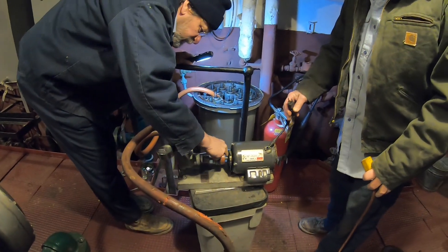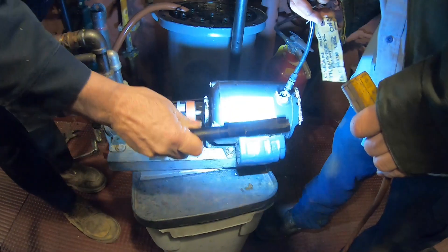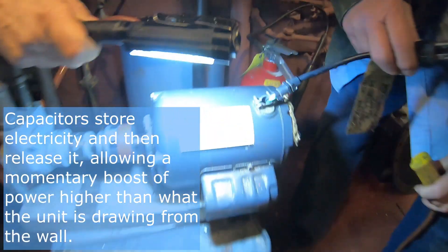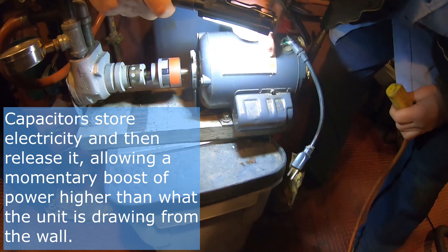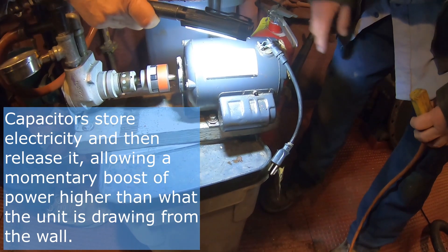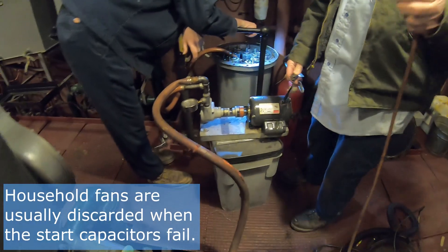But it's pumping. Why is it kicking out and off is what I don't understand — it's a pretty heavy load. What's it need for starting amps? More than we have? Horsepower amps — what's it say right there? Cool. Amps is 8.4 amps. Well, this on 120. So in theory, we're doubling, right?